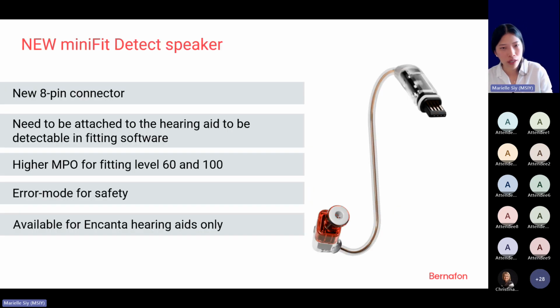And here are some more things you should know about the miniFIT Detect speakers. First, the new 8-pin connector. This is the part that you see there. So the 8-pin connector actually looks like a very small USB stick, and this allows the speaker to store information, including the serial number of the speaker, the fitting level, the length, the side, but it also stores the calibration data, which allows the Encanta to adjust the gain based on this data to compensate for any deviations in the output of the speakers.